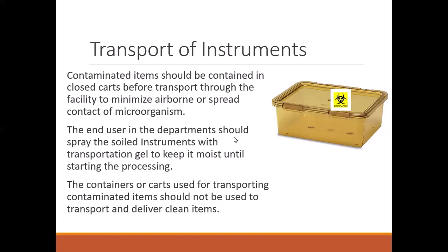We should not wash the instrument inside any area in the hospital. There is a special spray that will prevent blood and body fluid from sticking to the instrument. So we have to spray and directly transport to the CSSD department. So we should not wash. You should have 2 boxes, one for used instruments and the other for receiving sterile instruments.